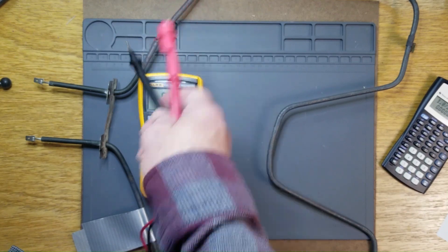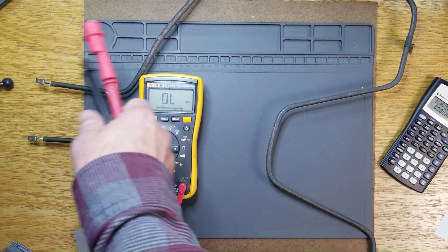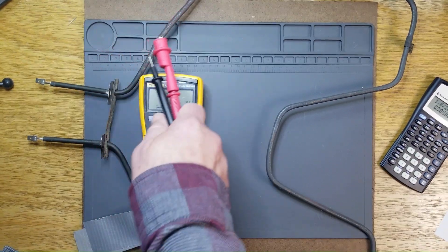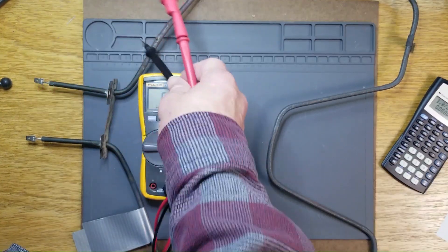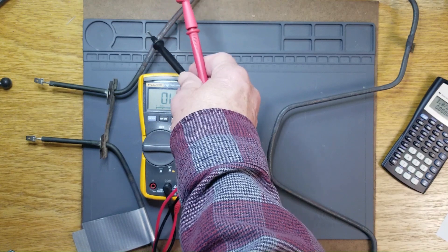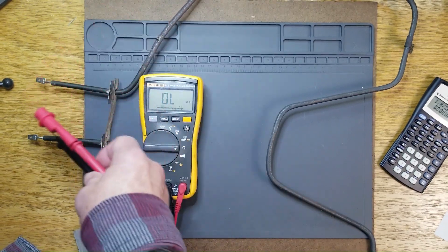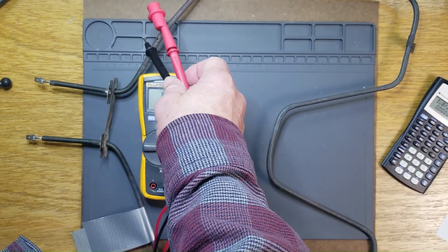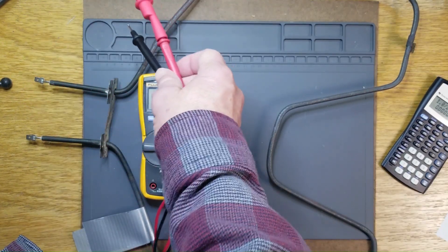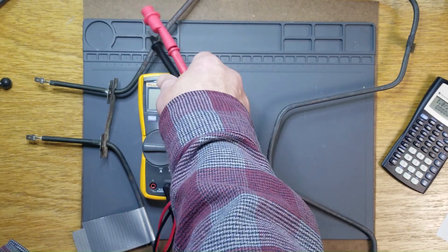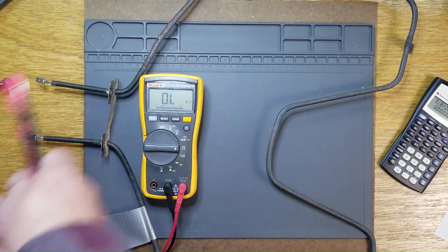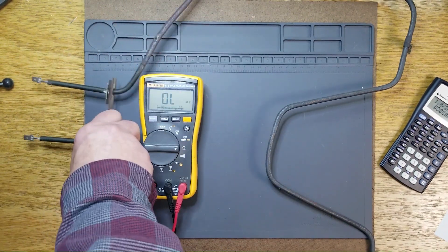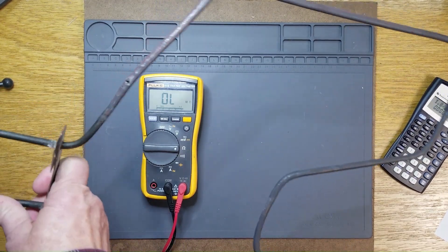So obviously that resistance reading of 20 megaohms is not anywhere near representative of how much current would flow through this when its insulation broke down. So when it reached 120 volts, it crossed the threshold where the insulation went from 20 million ohms down to about 4 ohms, minimum of 4 ohms. So that's one way that ohms can lie to you as well.